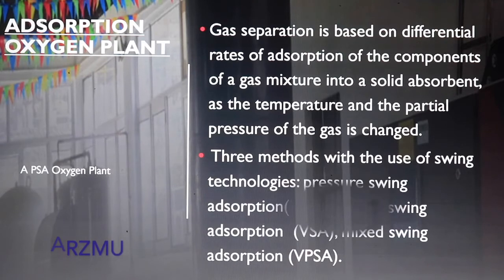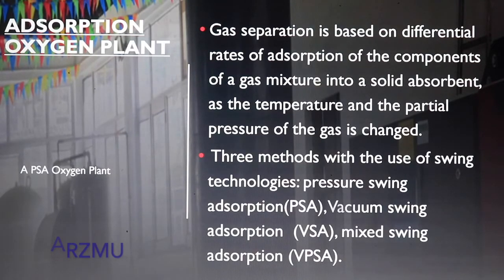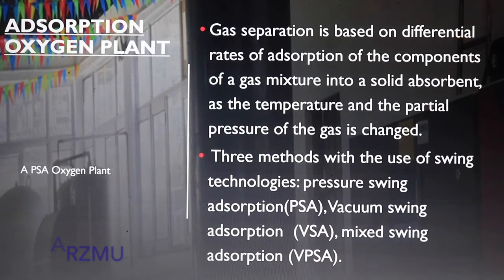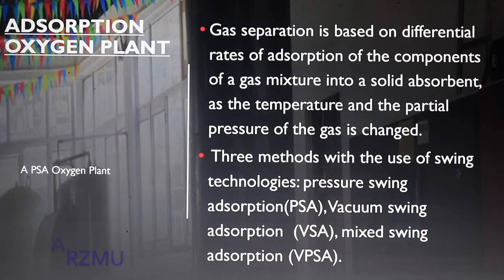Today there exist three methods of arranging the adsorption based air separation process with the use of swing technologies: pressure swing adsorption (PSA), vacuum swing adsorption (VSA), and mixed swing adsorption (VPSA).